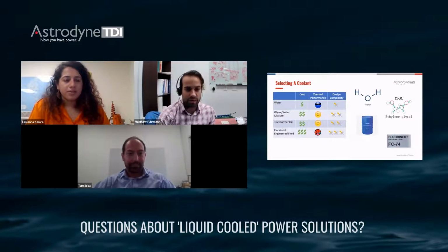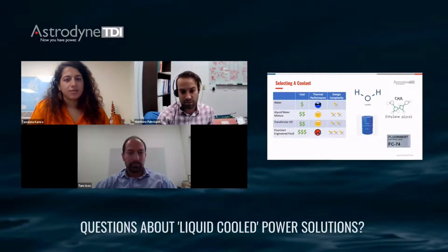When you're selecting your coolant, there are environmental considerations that need to be taken into account—first, the thermal characteristics of the fluid itself and its compatibility with the plumbing materials. As you can see on our chart here, in most applications, distilled or deionized water is the best coolant medium due to its heat carrying capacity, its low cost, and its availability. However, the trade-off is that if you're designing for an application where the environment will drop below 0 degrees C, you don't want to use water there because it can freeze.